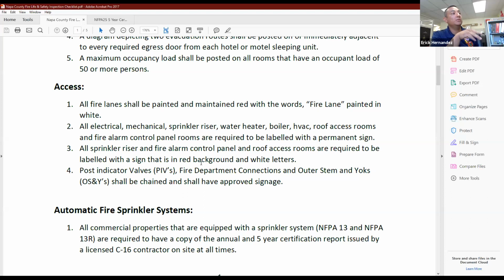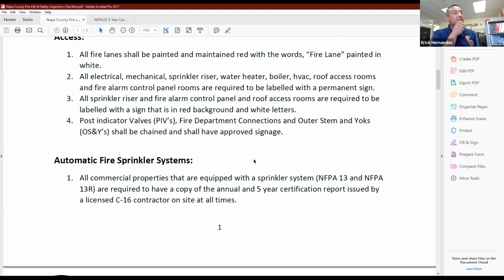Sprinkler riser and fire alarm control panels, roof access. So anything related to fire protection systems has to be properly labeled and identified. So all signage shall be red background, white letters at the doors so that we can properly identify them. For instance, electrical and mechanical rooms, even though they're required to be identified and have proper signage, they don't have to meet a certain criteria or a certain color. They could be any color you want as long as they're in contrast and we can identify them. But anything related to fire protection systems has to be red background, white letters. And then PIVs, post indicator valves, and fire department connections shall be chained and have appropriate signage. The reason why we say chained is because the last thing you want is for someone to turn off your sprinkler water, and during an emergency your sprinkler system is not going to work properly. Okay.